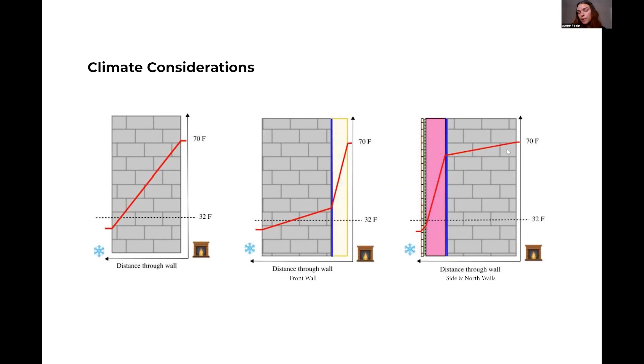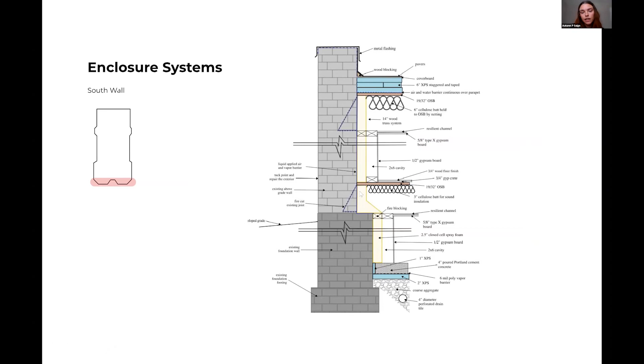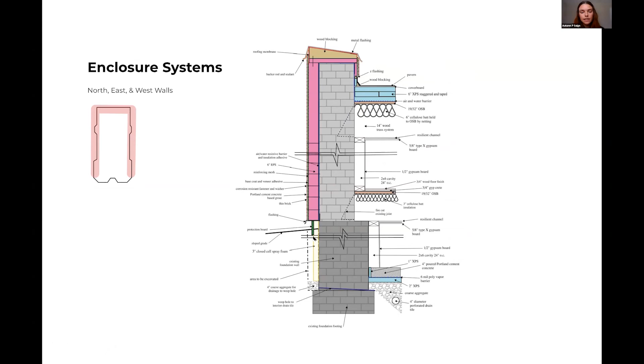So the best approach from a technical standpoint is to insulate from the exterior. But because of our guiding design principle of preservation, we're taking a unique approach that combines the two thermal control strategies. To the south, where there's the decorative facade, we're taking an interior approach using spray foam insulation. For the remaining walls with the deteriorated utility brick, we're taking an exterior approach using a drainable EIFS system that integrates to below-grade exterior insulation, spray foam applied using an excavationless technique developed here at the University of Minnesota.